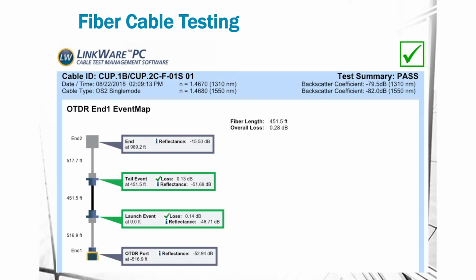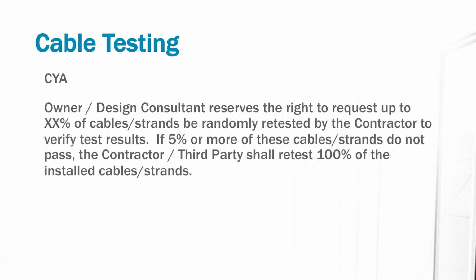All of the overall loss has to add up, and it has to be below a certain threshold. Part of the phased approach is that if there's an issue, it'll tell you where in the circuit that issue occurred. So if it's already installed and you're testing it, you can pinpoint where that failure happened, so when you pull another fiber cable through, hopefully you don't replicate that damage.